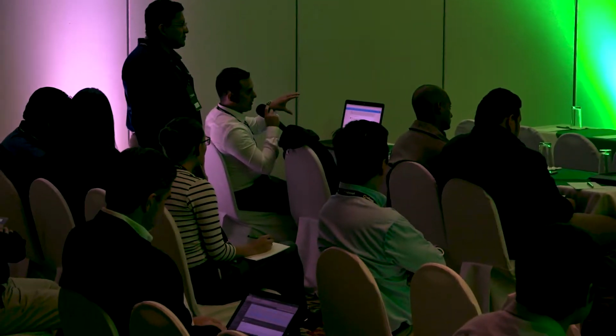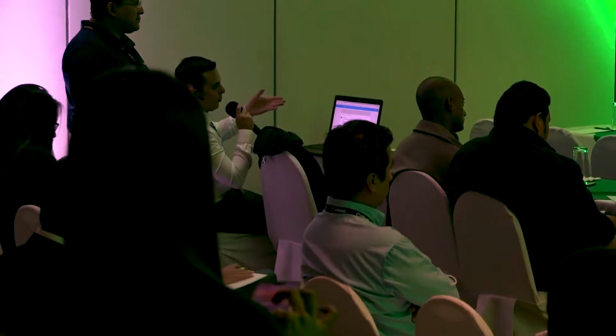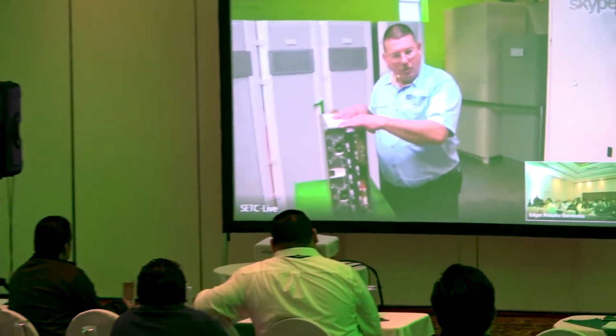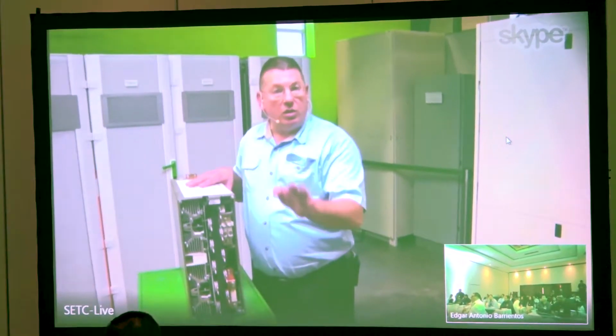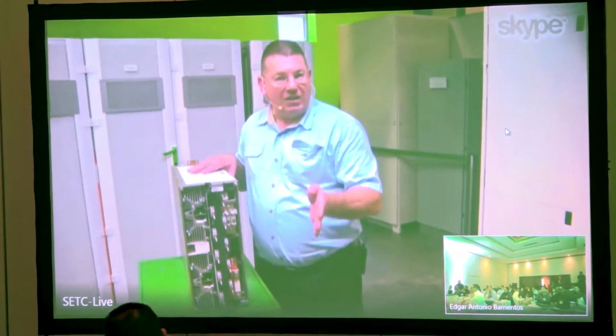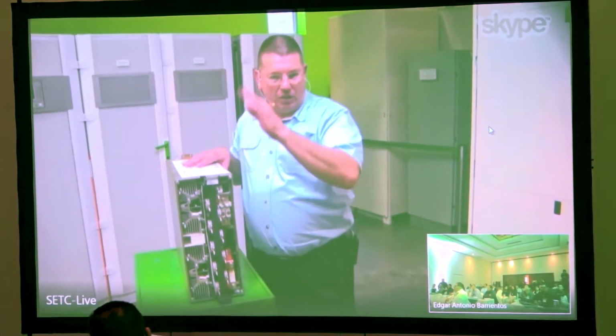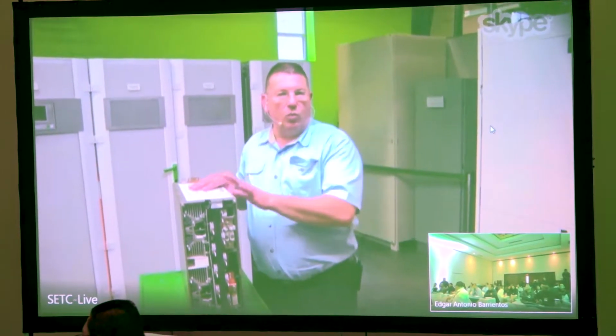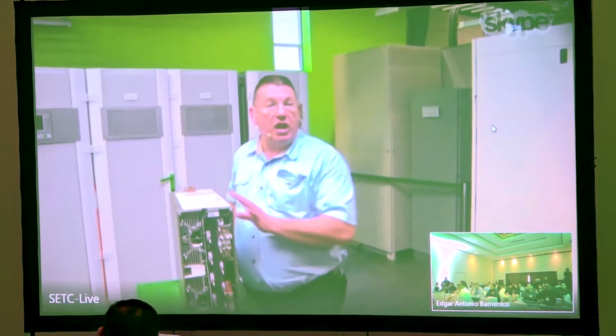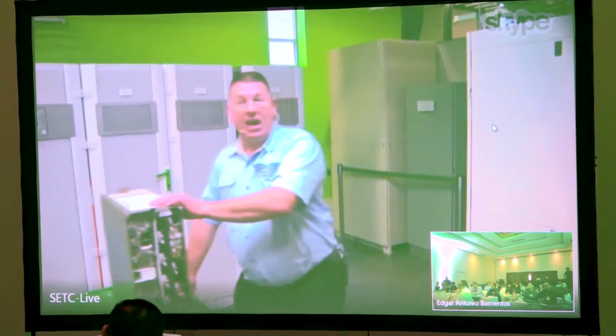When you do that change, that switch from the UPS, does that imply any downtime or the UPS keeps on working? So if we have to change these, the power blocks? Yeah, that one. So the UPS has to be in a maintenance bypass state. So it's because there's too much energy inside the cabinet.